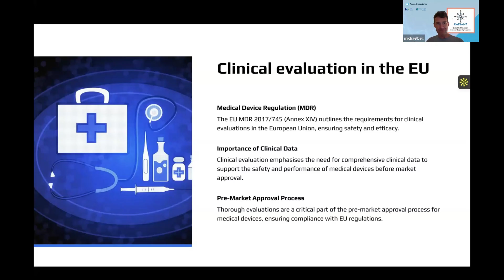Well, what does that mean? It means that there's a number of notified bodies who perform the assessments. They're independent of the EUDAMED and so on, right? But they all need the same thing effectively. They all need you to perform the clinical evaluation, have the clinical evaluation plan, provide the clinical evaluation report, and make sure that's sufficient for your device. Okay, and that's all around pre-market for the EU.